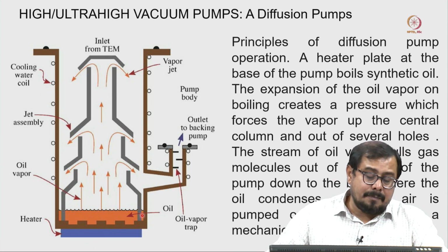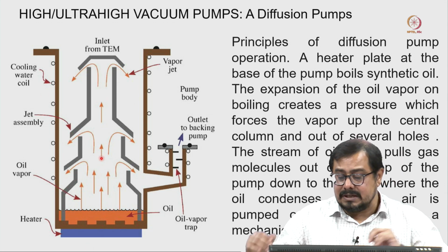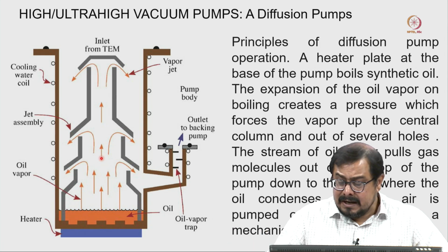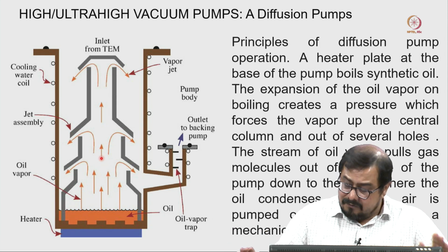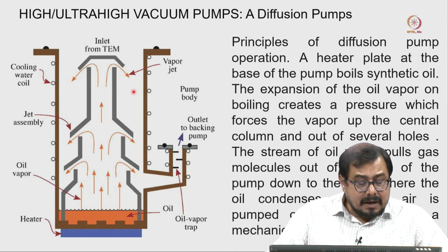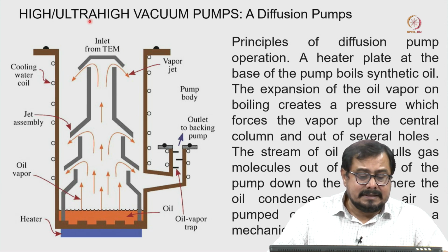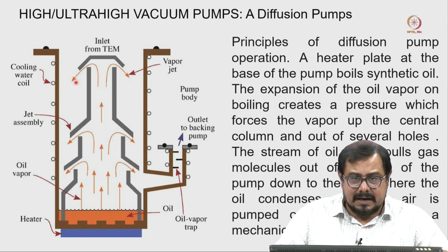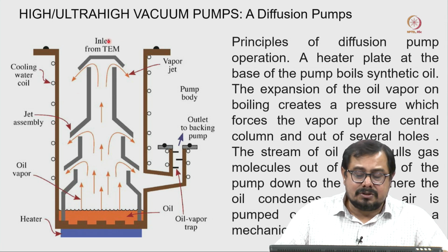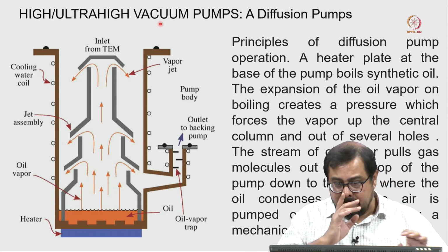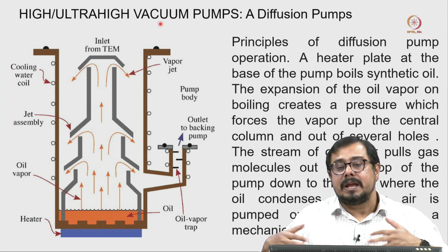The oil diffusion pump is one of those, not generating too much noise and giving a very high vacuum. But the major problem is that sometimes because of this oil, it contaminates the microscope column with oil.